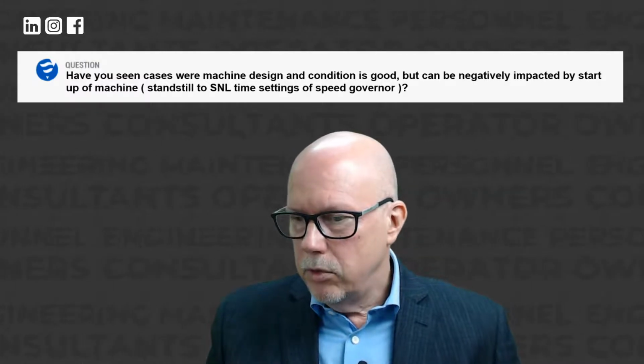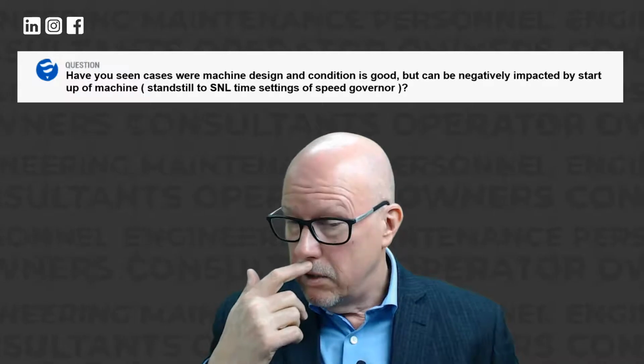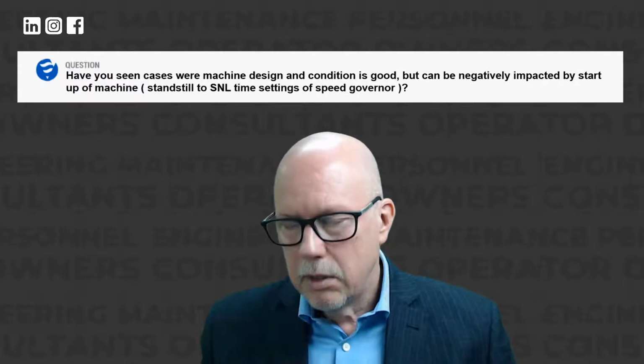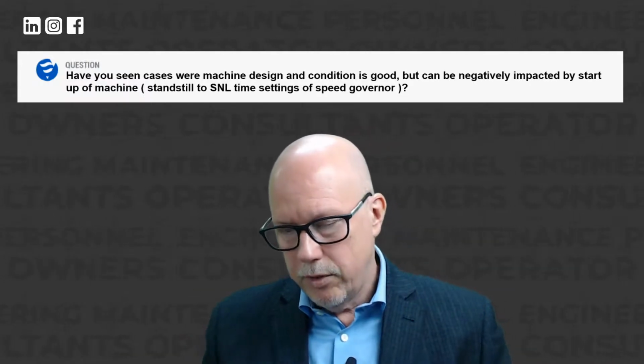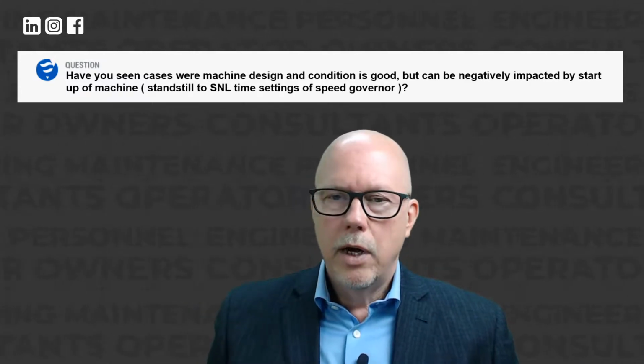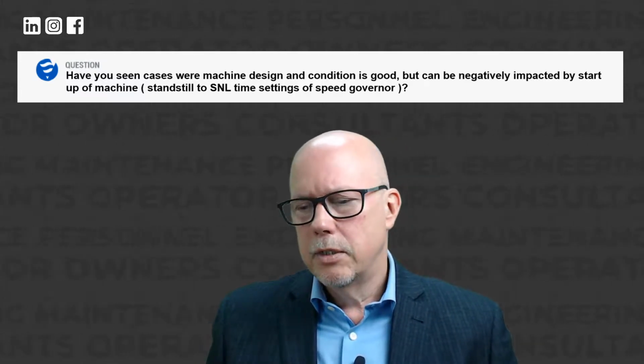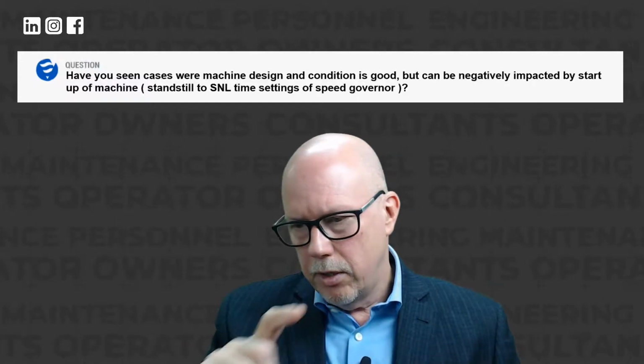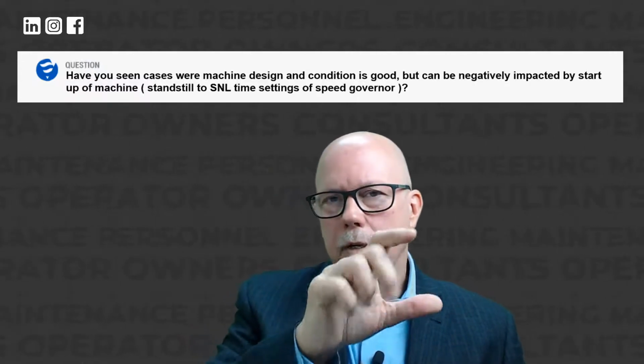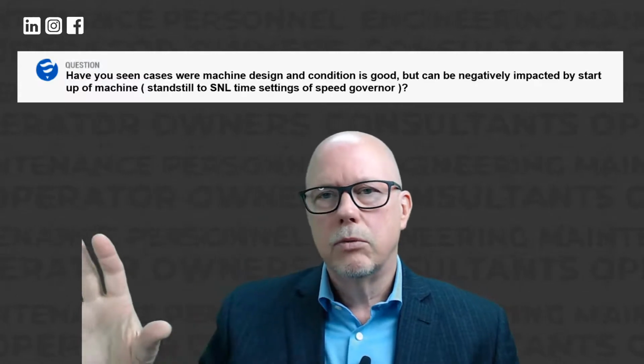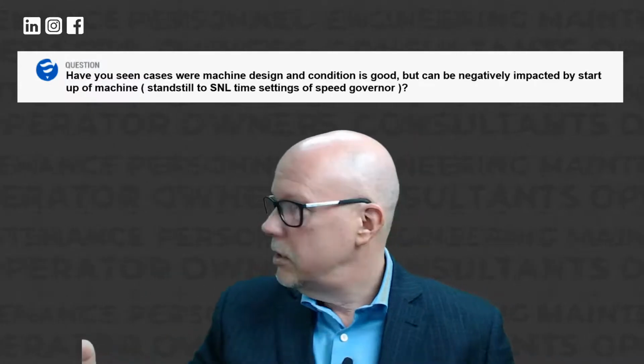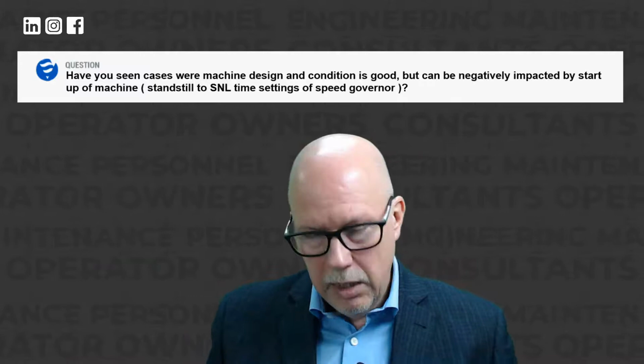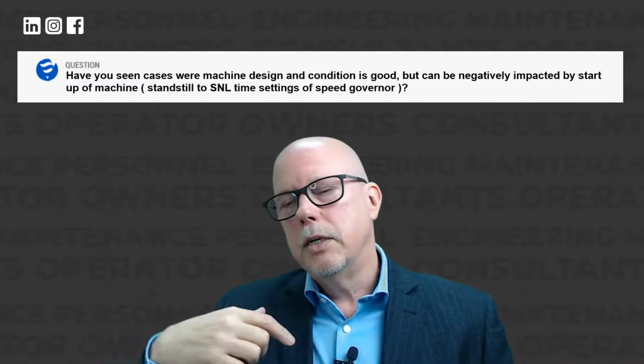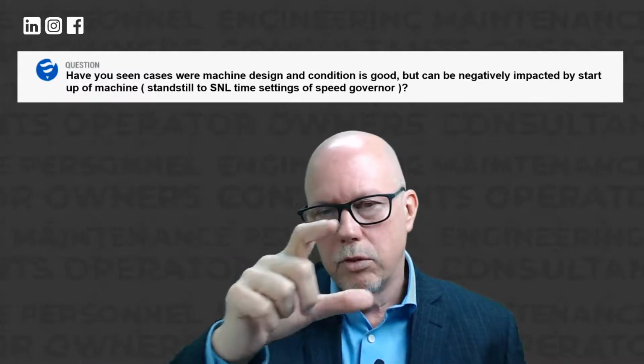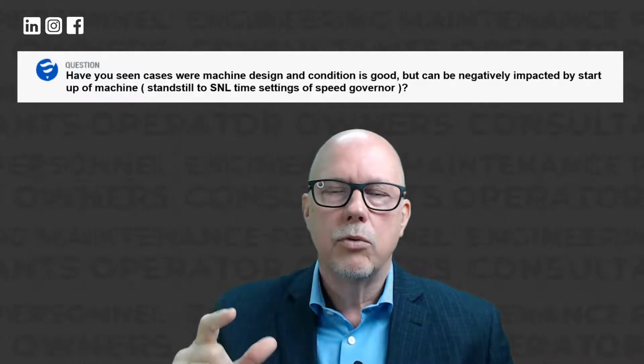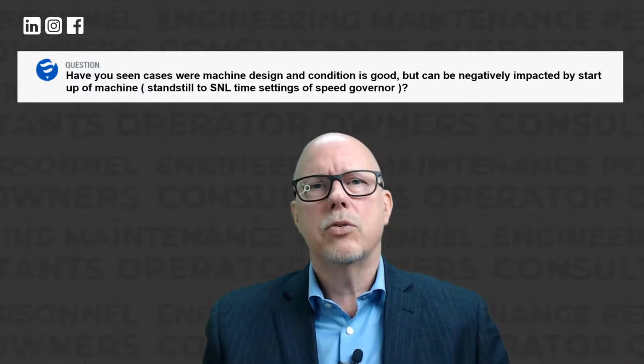We have another case, again about looking at the results. It was another power station in Brazil, quite a few years later, where we were doing some tests commissioning the system and the unit, and I picked up a startup. If you looked at the startup at full scale, it looked completely normal, with the air gap decreasing because of centrifugal forces. But if you zoomed in to the initial rotations, you could see how the rotor was significantly distorted.